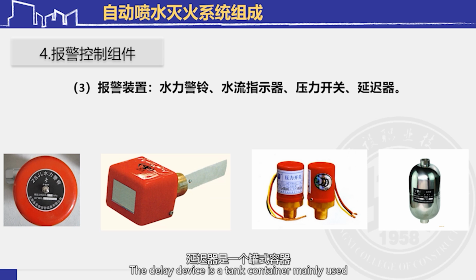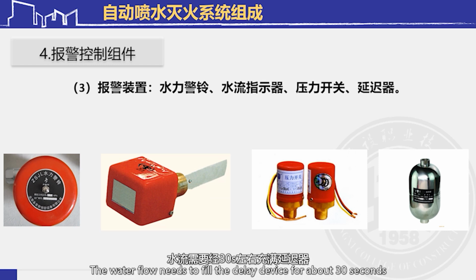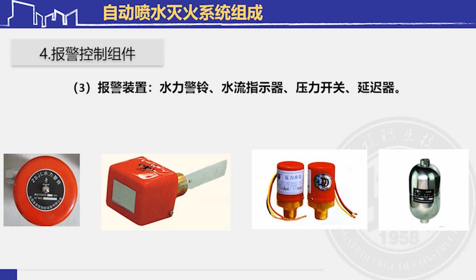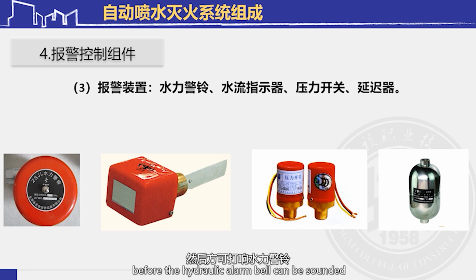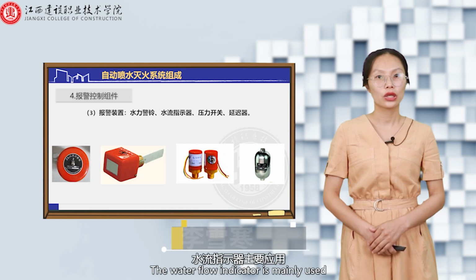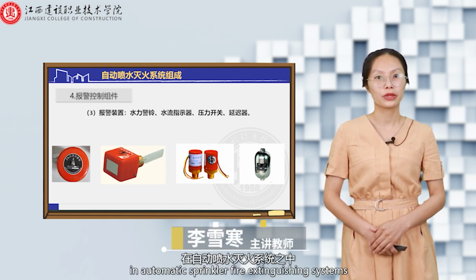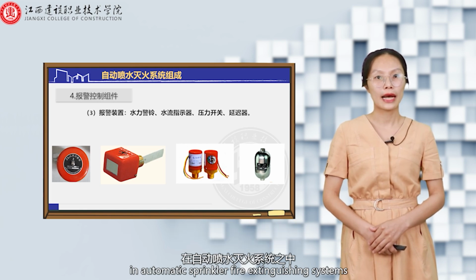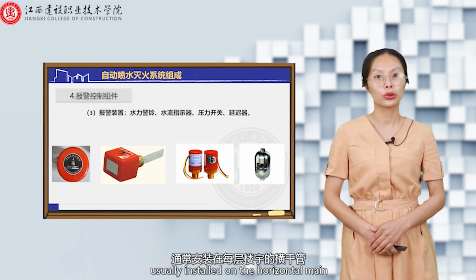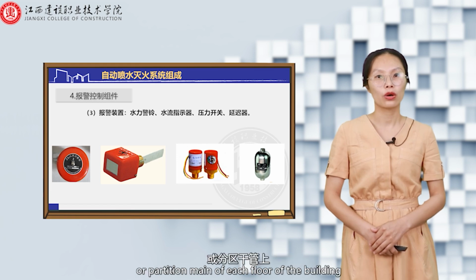The delay device is a tank container mainly used after the alarm valve is opened. The water flow needs to fill the delay device for about 30 seconds before the hydraulic alarm bell can be sounded. The water flow indicator is mainly used in automatic sprinkler fire extinguishing systems, usually installed on the horizontal main or partition main of each floor of the building.